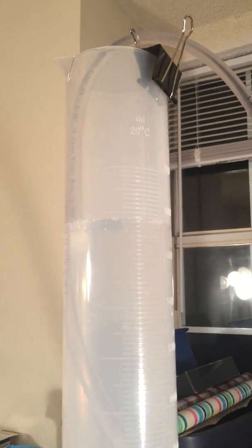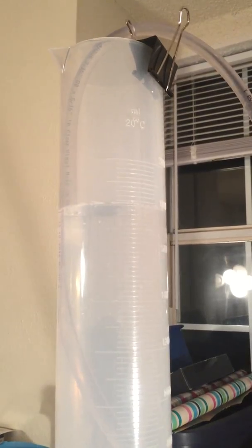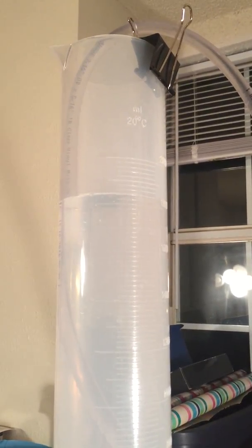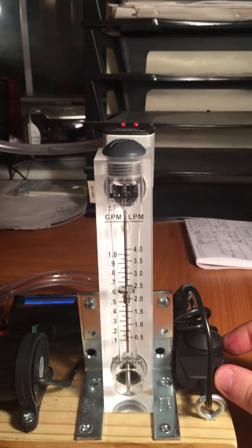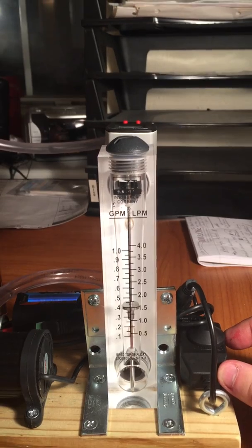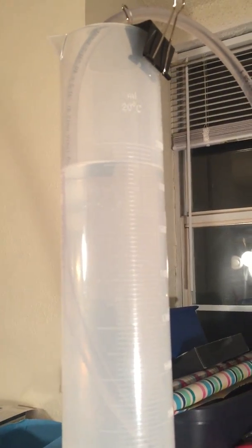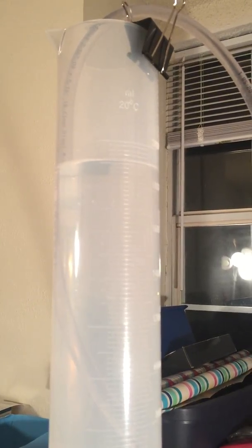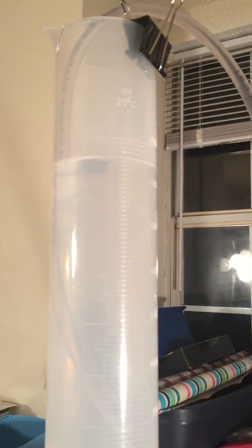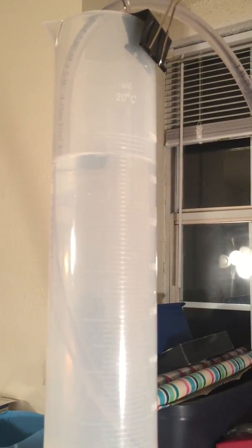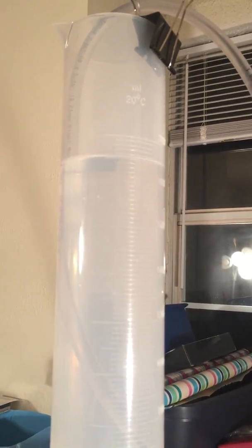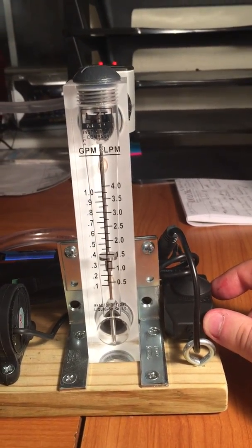And as I'm doing this, I'm also looking up here at the water column. You'll notice now the water column is increasing, and it's increasing pretty quickly. So I've now got the pump pumping too fast. So I want to bring the volume flow rate down, and we'll take a look back up here and see what's happening. So that actually looks pretty good, right? The water level's falling just ever so slightly. So I need to increase the pump volume flow rate just a little bit.